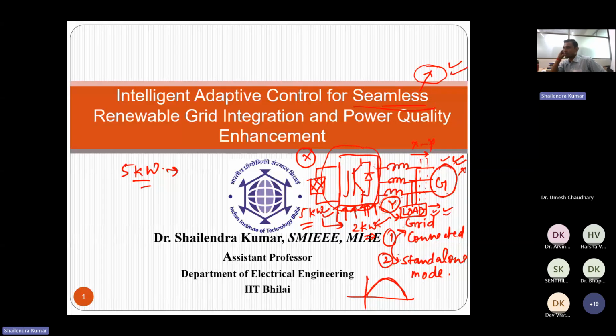So to match this load demand, if grid is there, then the rest of the power, like 3 kilowatt, we can feed to the grid. But what would be the option when you have this small system and 5 kilowatt generation is there during standalone? That is the challenge while we transfer this grid connected system to standalone.